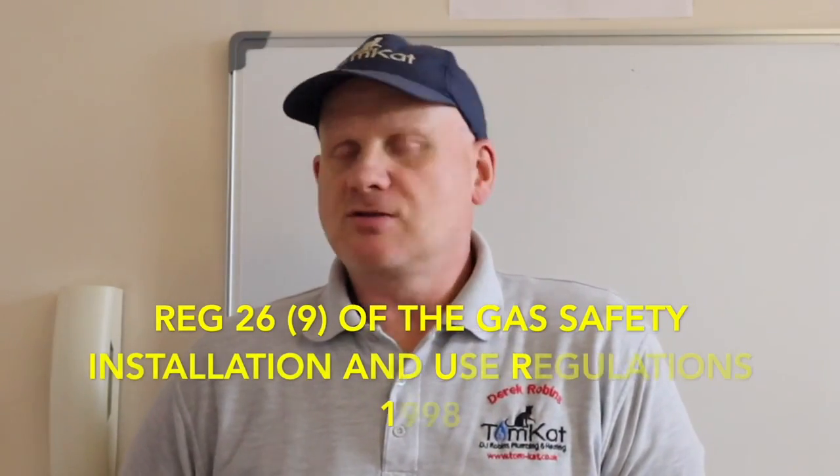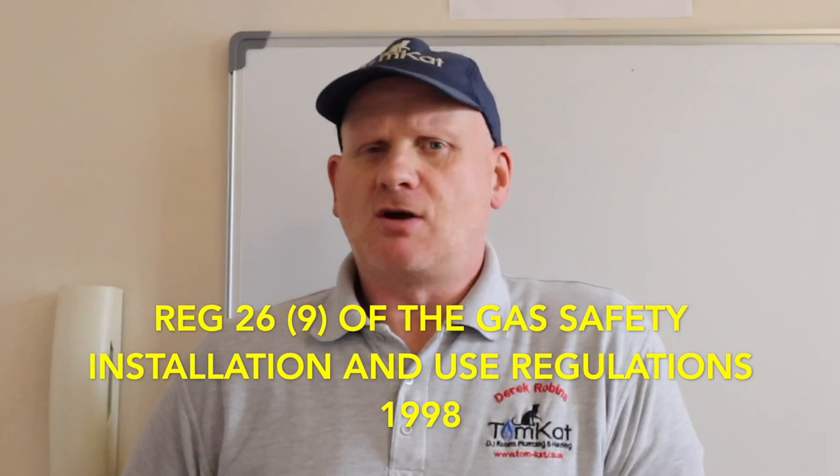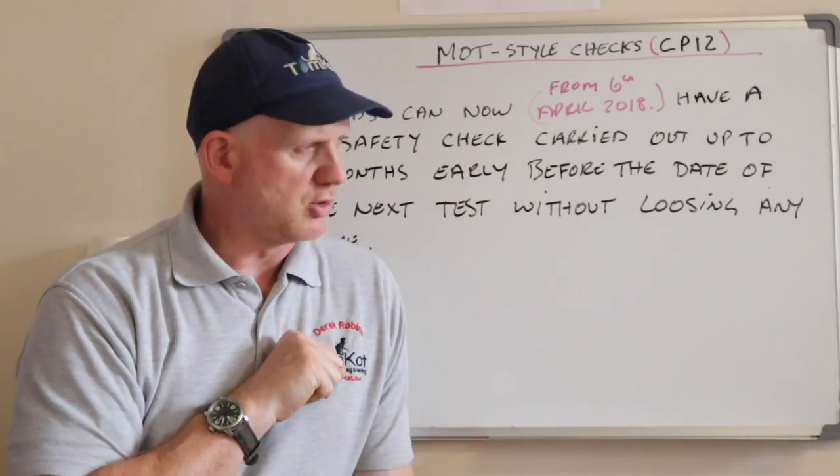According to regulation 26(9), you don't technically have to do a tightness test on a landlord's report, but the landlord has a responsibility to have their gas pipework integrity checked at least once a year. That's why we incorporate a tightness test into a landlord's report — but technically these should be two completely separate activities carried out separately. We tend to let landlords off and do both at the same time.